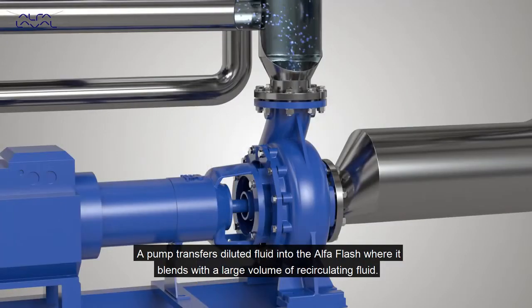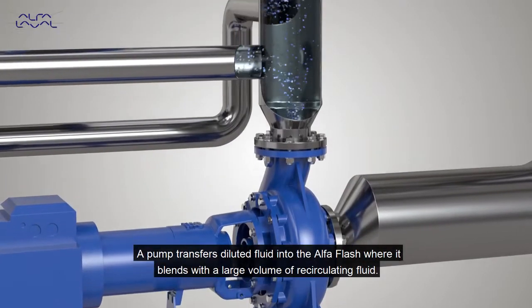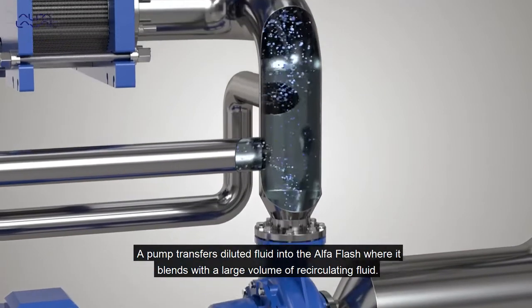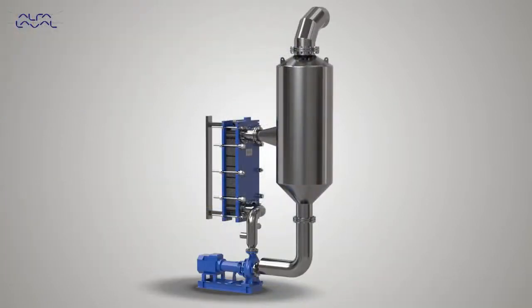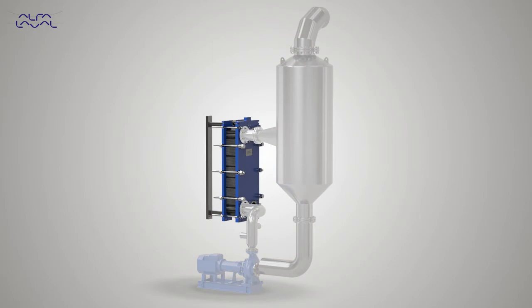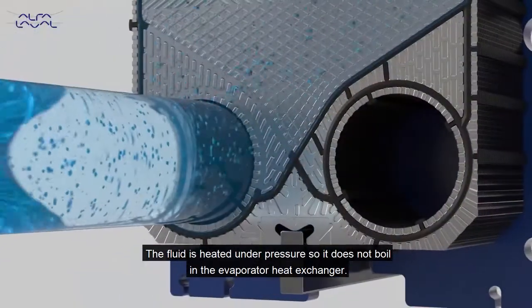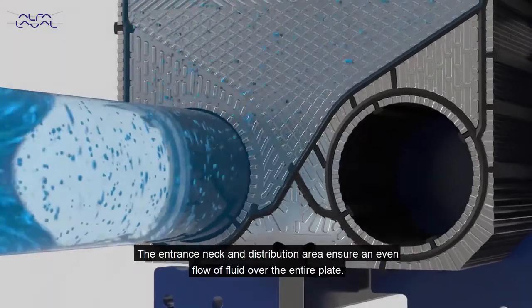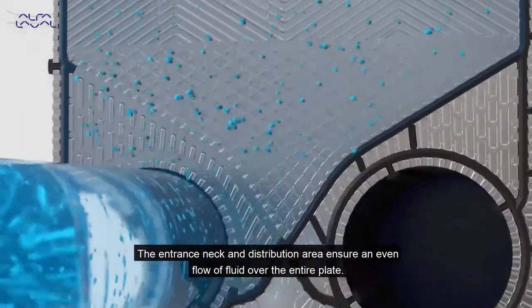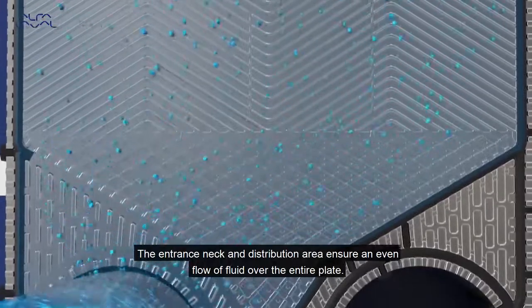A pump transfers diluted fluid into the Alfa Flash where it blends with a large volume of recirculating fluid. The fluid is heated under pressure so it does not boil in the evaporator heat exchanger. The entrance neck and distribution area ensure an even flow of fluid over the entire plate.